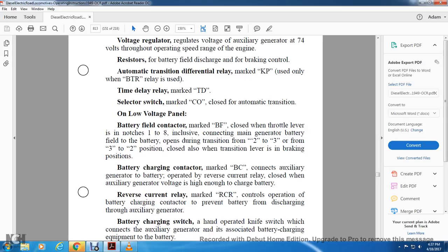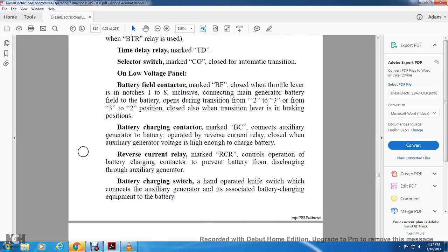Battery charging contactor, marked BC, connects the auxiliary generator to the battery. It is operated by the reverse current relay and closes when the auxiliary generator voltage is high enough to charge the battery. Reverse current relay, marked RCR, controls operation of the battery charging contactor to prevent the battery from discharging through the auxiliary generator. Battery charging switch is a hand-operated knife switch that connects the auxiliary generator and the battery charging equipment to the battery.